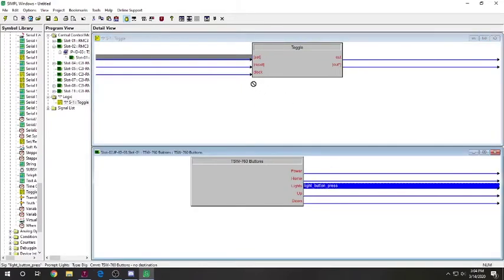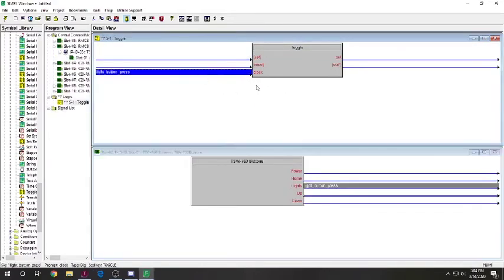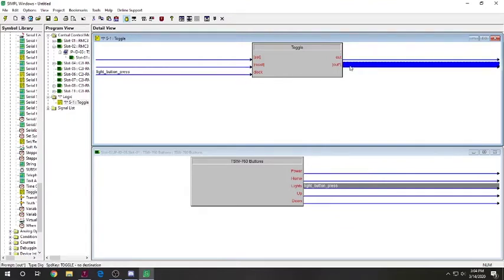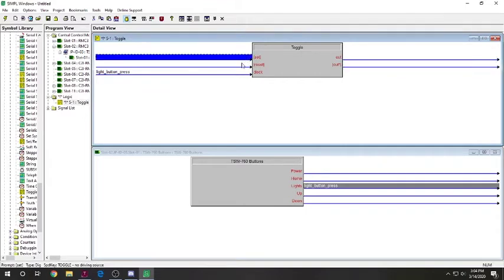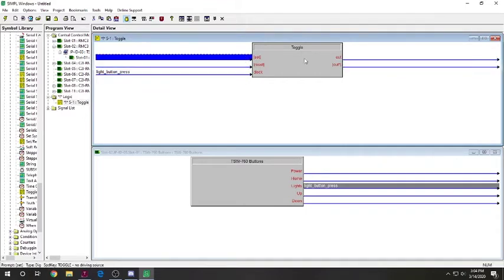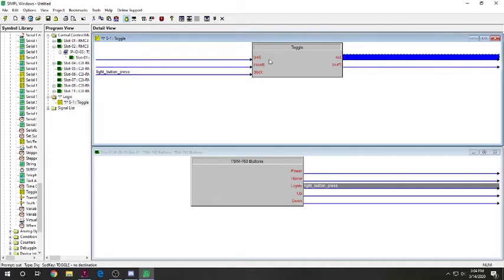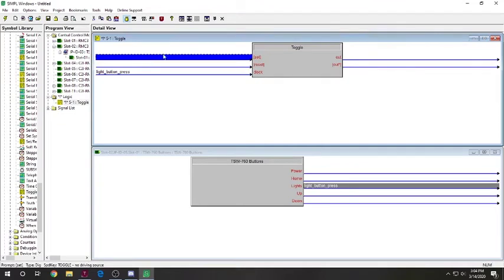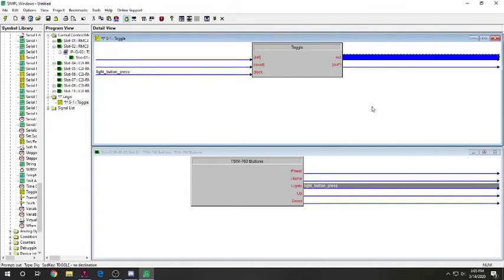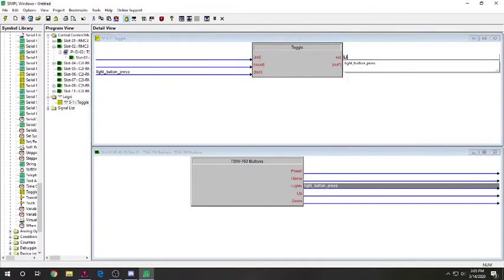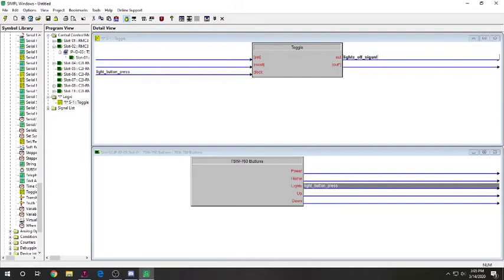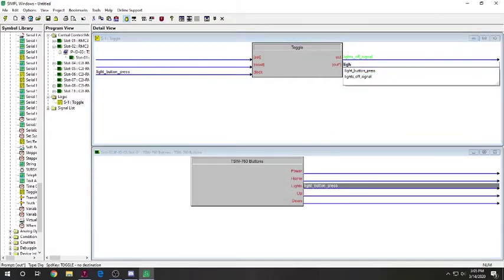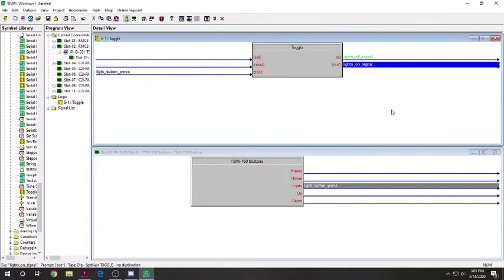So, we're going to start here. I'm going to close everything else out. We'll grab everything else in a second. Here we have the touch panel buttons. And on the lights, we're going to say light button press. So, that's one signal that we need. Now, we need the toggle. Because this light button press is going to feed into the clock. This clock is the actual toggle input. So, every time this clock goes high, it's going to switch between out going high and out asterisk going high. Now, you can also have light set and reset. This will automatically set this out to be high. And this reset will set this out asterisk to be high. This clock will just switch which one it is. So, that's where we want to get our input.